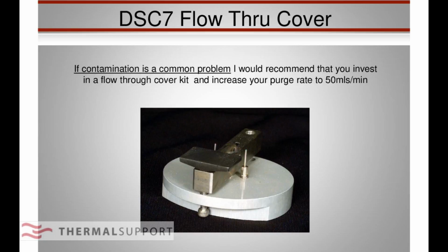If that's the case, don't stick with the standard cover. Get a flow-through cover, crank up your flow rates, get rid of that stuff. You will pay for it in a heartbeat rather than gradually deteriorating your sample cell. And if you have those kind of problems and you do not set your purge gas up and let it run without a purge, you're going to ruin those very expensive sample holders.